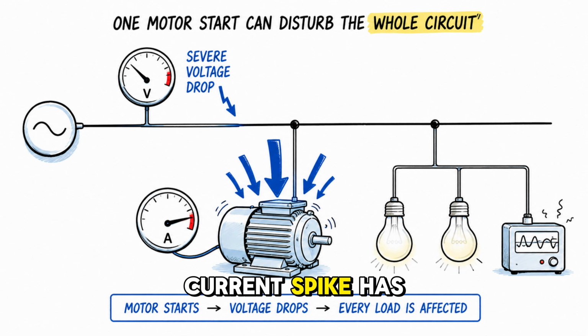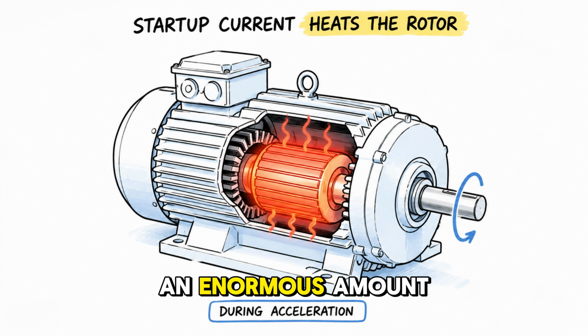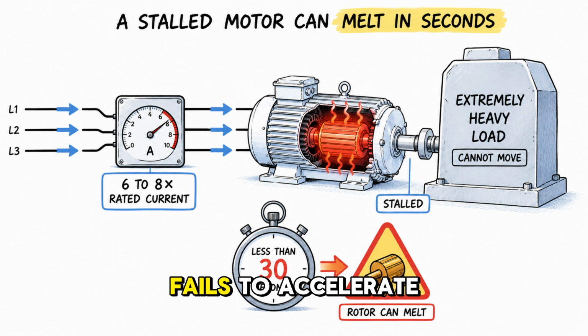This intense starting current spike has 2 serious consequences. First, it causes a severe voltage drop in the power supply that dims lights and affects every other load on the same circuit. Second, it produces an enormous amount of heat inside the rotor during the acceleration period. If the motor fails to accelerate, perhaps because the connected mechanical load is just too heavy to move, that starting current will continue indefinitely at 6 to 8 times the rated current. In a stalled condition like this, the rotor can reach destructive melting temperatures in less than 30 seconds.